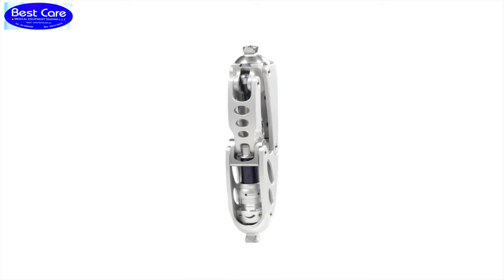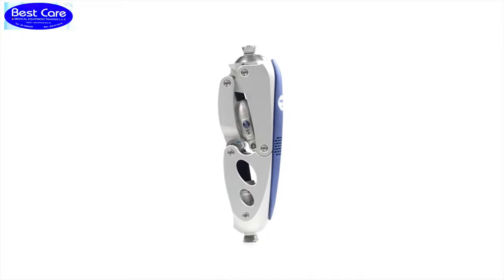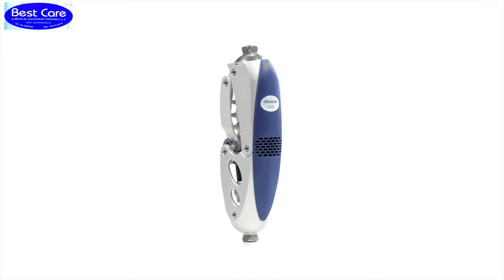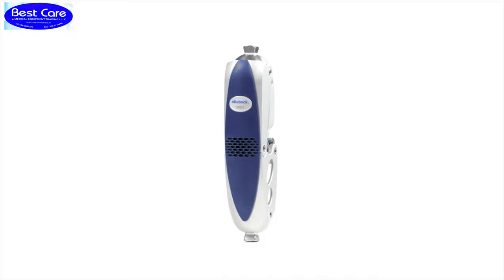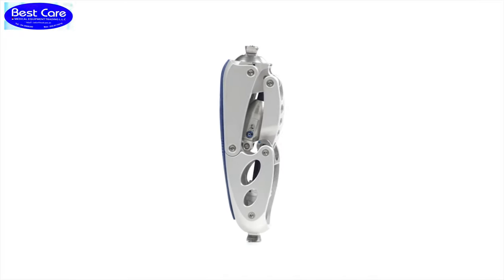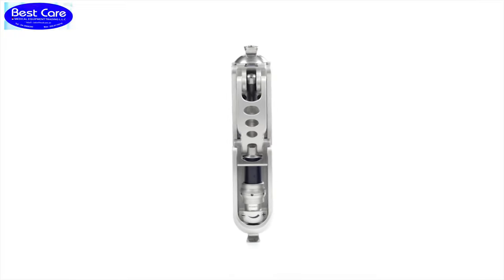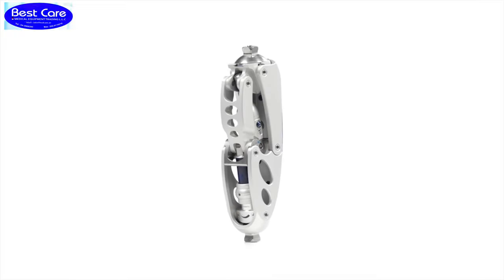The unique characteristic of the 3R60 is its ergonomically balanced stride, EBS, which allows for a cushioned stance flexion of up to 15 degrees taking place without initiating normal swing flexion. This stance phase flexion creates shock-absorbing comfort at heel strike as well as additional stability for the user.